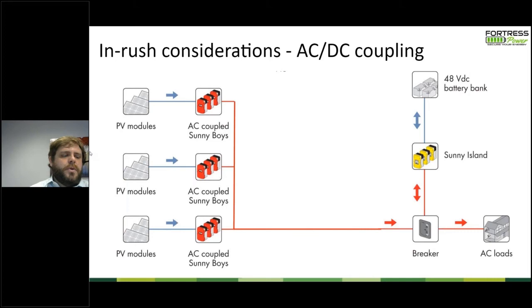And so in particular, when you're doing systems that have multiple AC coupled inverters or multiple DC coupled charge controllers, in particular on a battery that is only supposed to back up the home for not a day, but a couple of hours, you can trigger an inrush current error. And the solution for that is just to go a little bit easier at startup: turn the inverter systems on one at a time with a period in between, rather than turning them all on within just a second or two of each other.